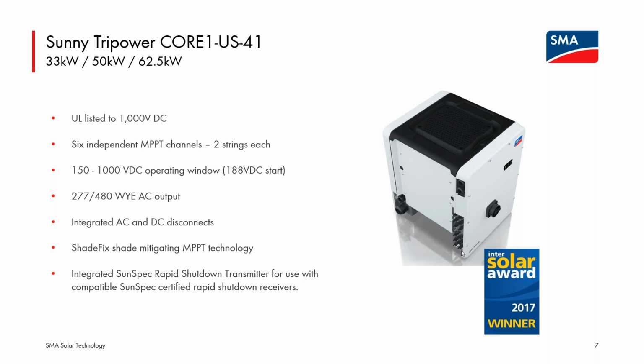Each of the 6 tracking channels has a very, very wide DC operating voltage window, 150 up to 1000 volts DC. Any voltage point within that window, the inverter will be making power from that input, and the 6 input channels can be working at different voltage points. So you have lots of flexibility for different string lengths, different orientations, different module types, in fact, if you want. If you're cleaning out the warehouse and have a lot of straggler modules and have 6 different strings of 6 different module types, that's fine. Those input channels, again, are handled independently by the inverter.